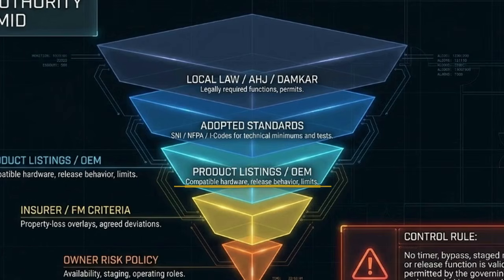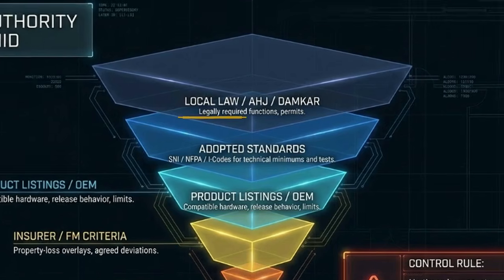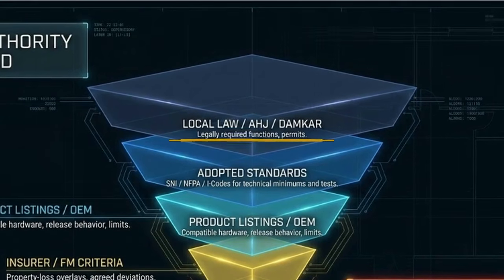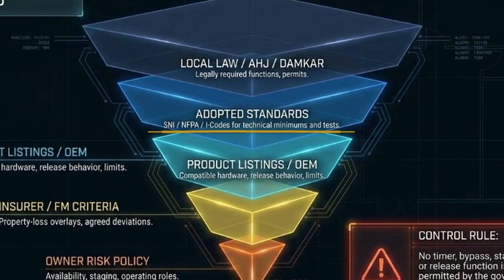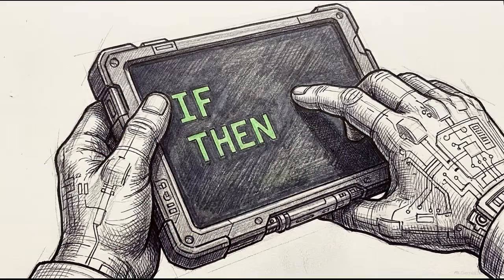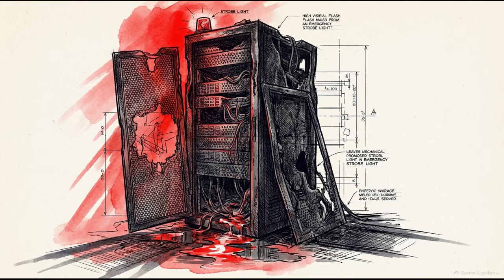Standard OEM equipment listings form the baseline, but local laws and the authority having jurisdiction, or AHJ, always sit at the top. Technical minimums are legally bound by those upper tiers, overriding any default factory setting. The matrix is the literal law of the building. If a scenario is missing from this contract, the system will not execute it. Ambiguity in these programming rows directly results in catastrophic hardware loss or life safety failure.